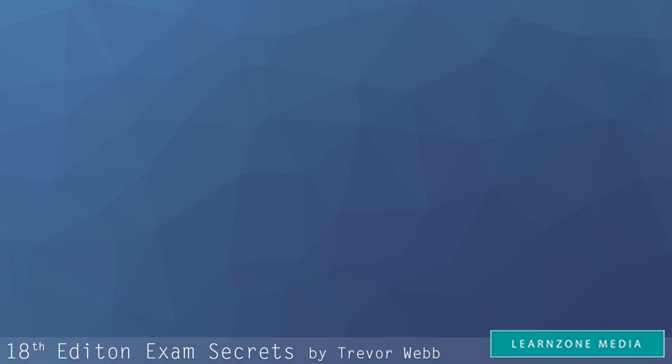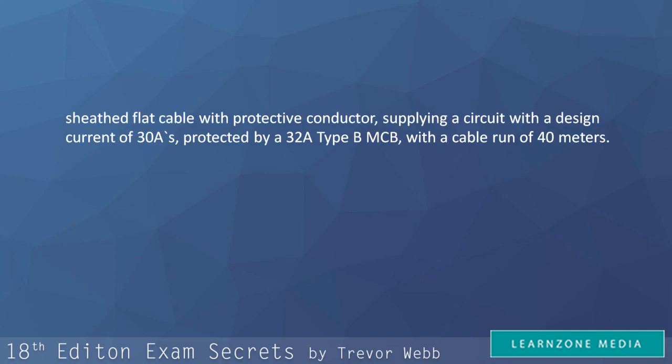The question might read, calculate the voltage drop for 2.5 millimetres square, 70 degrees celsius thermoplastic, insulated and sheathed flat cable with protective conductor, supplying a circuit with a design current of 30 amps protected by 32 amp type B MCB with a cable run of 40 metres.